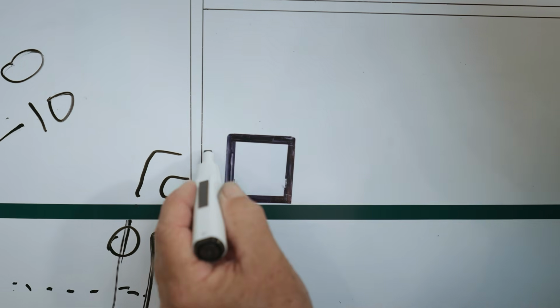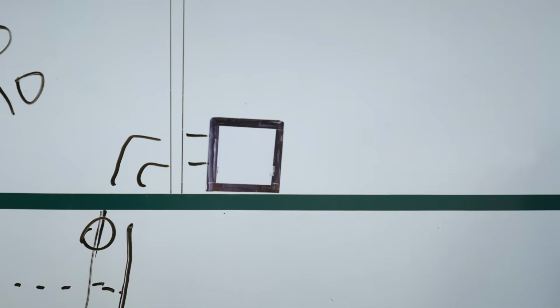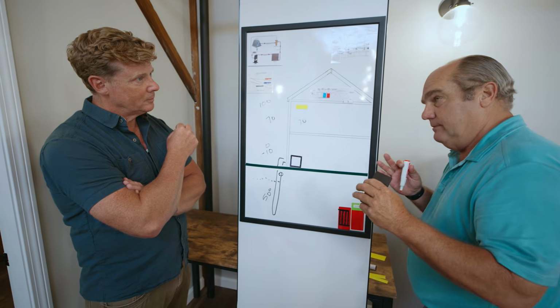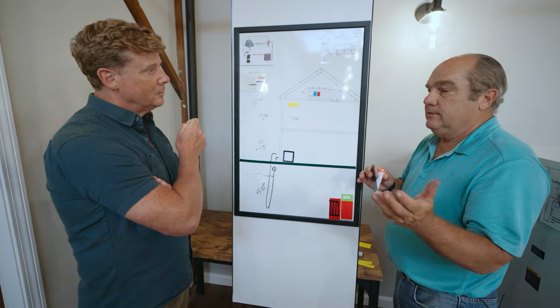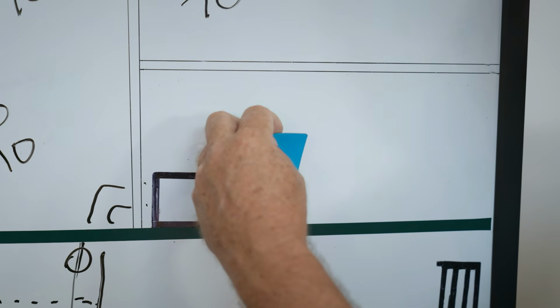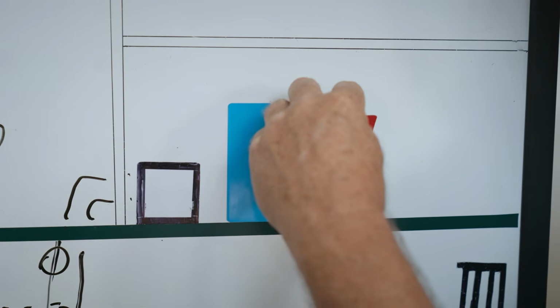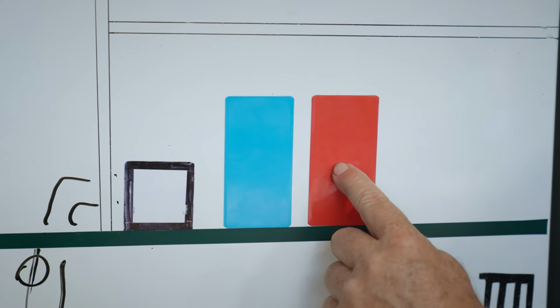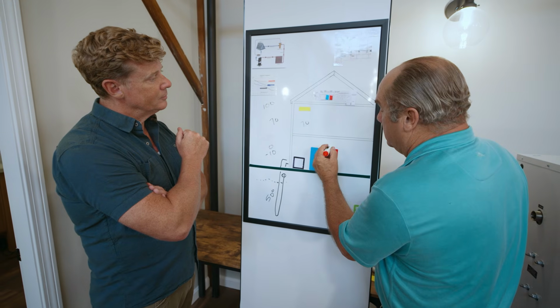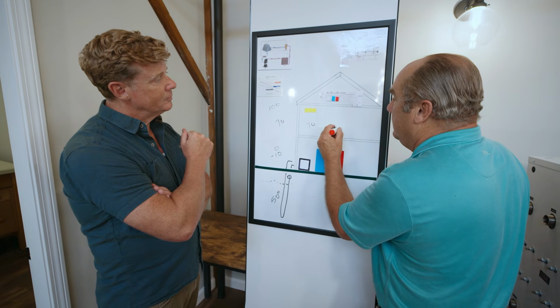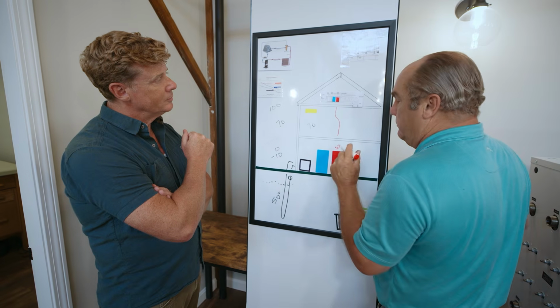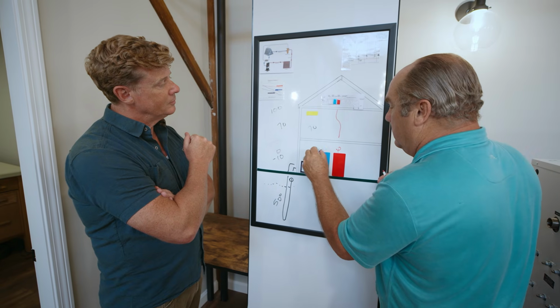Gotcha. The piping runs into this water-to-water geothermal condensing unit, which gives us a lot of advantages. We want the system to be able to heat and cool different parts of the building at the very same time. Right. So for that, we're going to introduce 2 tanks. One's a hot tank, one's a cold tank. Storage tanks, essentially. Absolutely. So now what happens is you can send heated water up to the coil in the air handler right here. So too on the cold water side. And it goes up here.